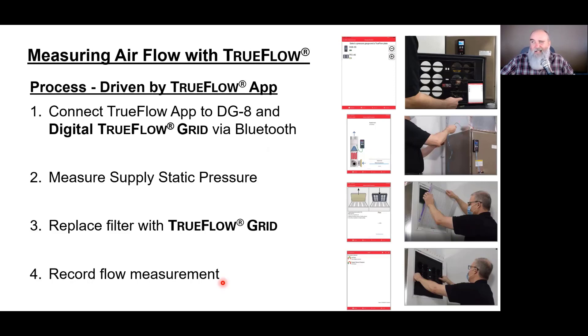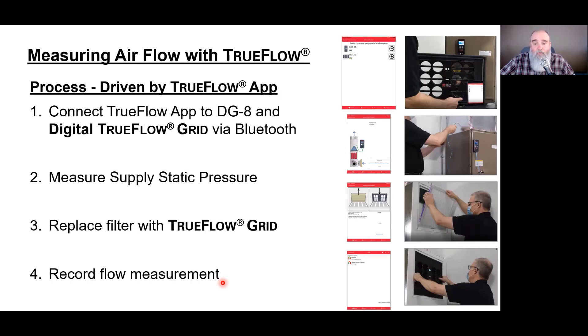You might be wondering how it knows. It's math. What we're able to do is compensate for the difference in the pressure drop across the filter and the TrueFlow grid and apply some math to that. What we're doing is measuring all the air that's moving through the system — all the air that would be moving through the filter is now moving through the TrueFlow. The result gives us an accurate measurement of airflow.